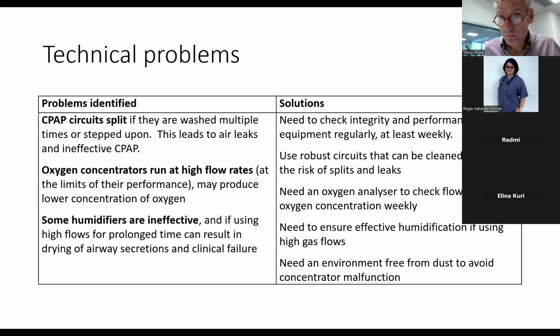Usually you don't need to, maybe 8 litres per minute or 6 litres per minute in total, 5 and 5 or whatever. But usually don't aim to run it at the maximum performance, because it will in time lead to fatigue. And also check your concentrator to see that the oxygen outflow is delivering 93 or 95% oxygen, what you aim it to be.